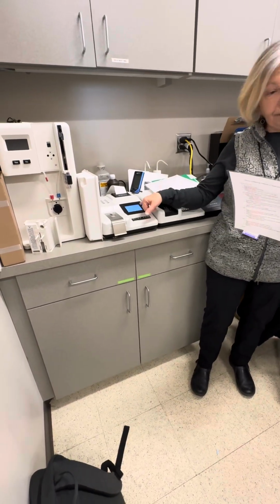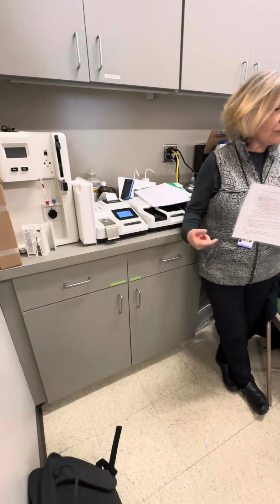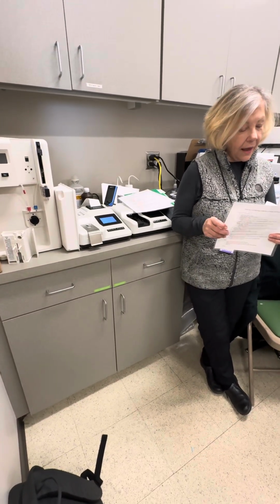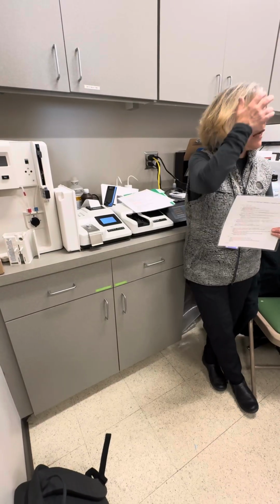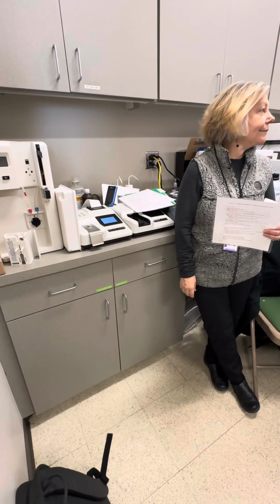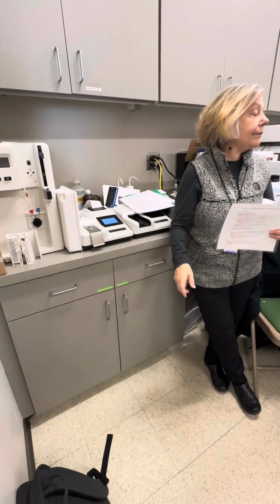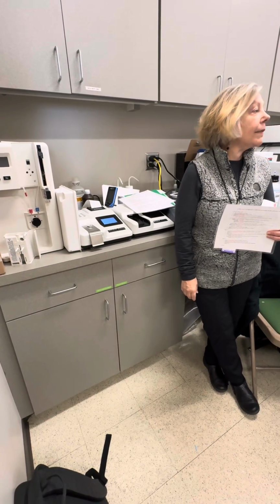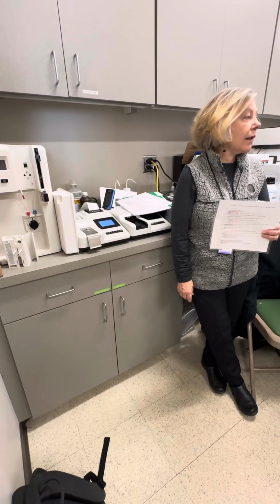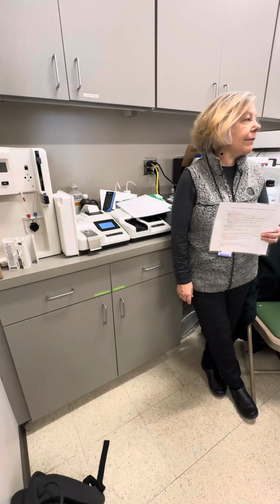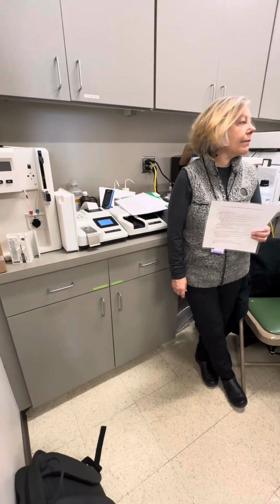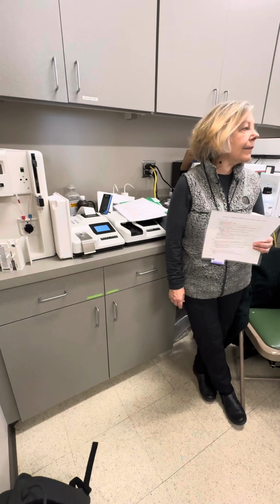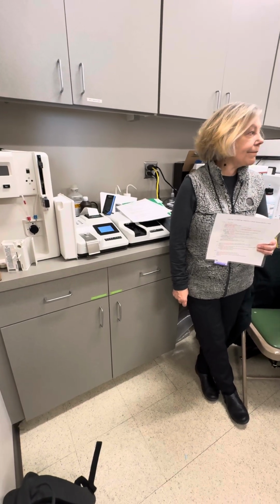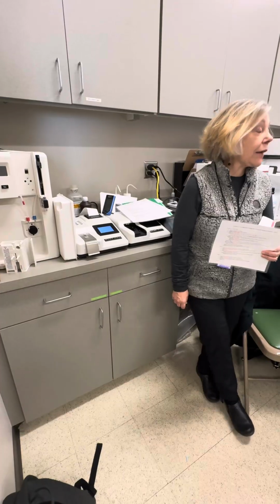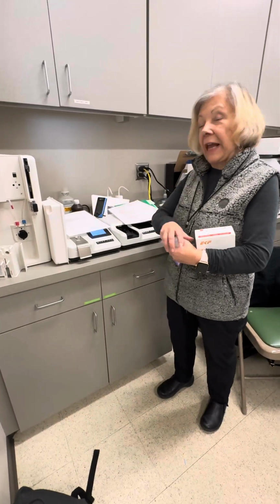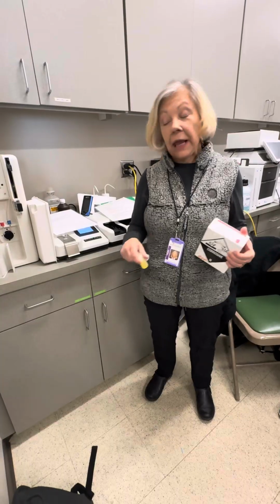And here's your curve. It stores that, says, okay, I know what a blank is. How often do you have to do a curve? Only when the QC is out, or you see a trend. You do it once per lot. Set your curve, it's in there, then it's always there, and only if your QC's out or you see a trend, then you make a new curve with standards. And it resets.